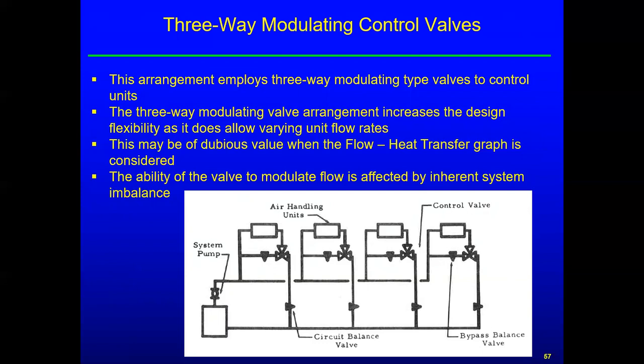So these have, each valve has really an infinite number of positions, from full flow to the coil to fully closed flow to the coil, and that's under the control of the thermostat. It increases design flexibility as you get these varying flow rates. The advantages may not be as significant as you may first think, because there is some inherent instability and imbalance, as we'll illustrate on the next slide, with a modulating three-way valve.